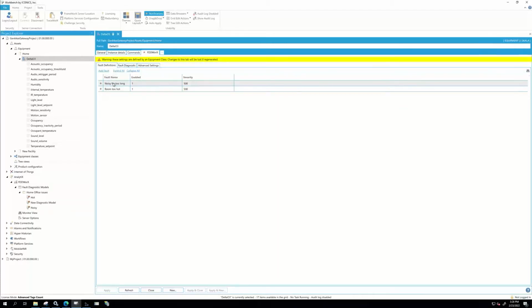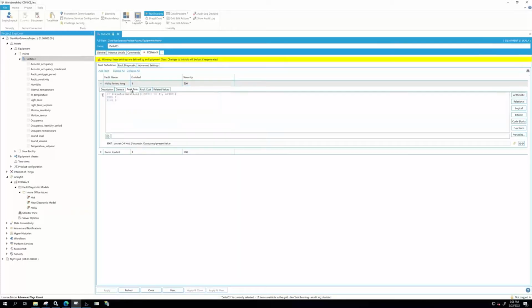And in this case here, I've created two sets of faults. So if we take a look at, for example, this one here, the fault rule for that was that if the occupancy, which is a measure of the sound level, is in alarm for more than 1 minute, then set an alarm. So this simple fault rule is simply adding a time specification. It's not just that there's an alarm now, but rather if this thing has been alarming for a whole minute, then there is a fault.